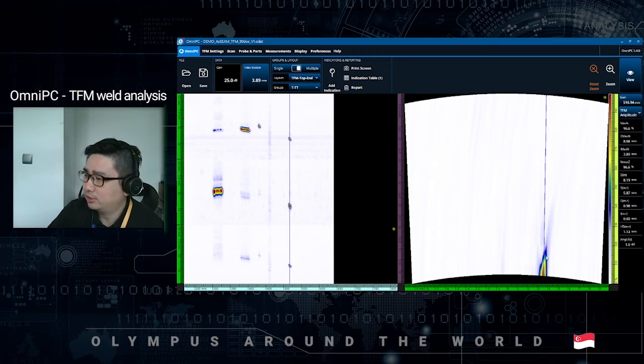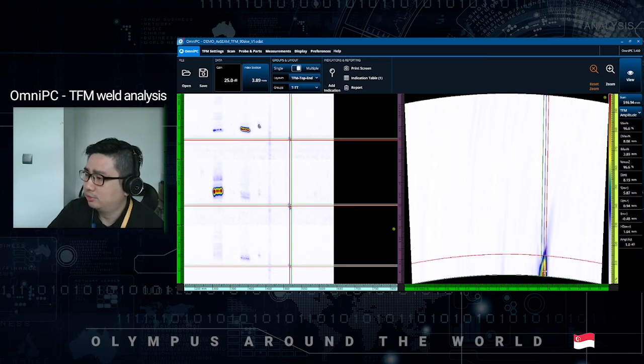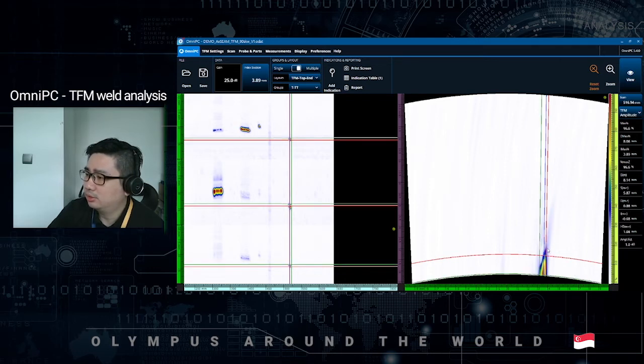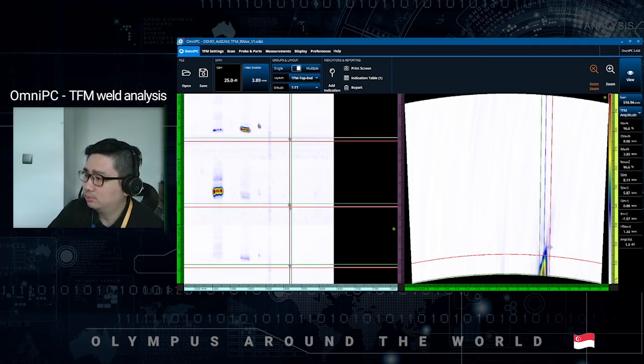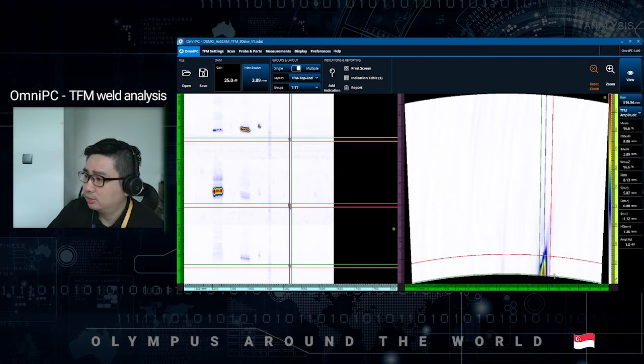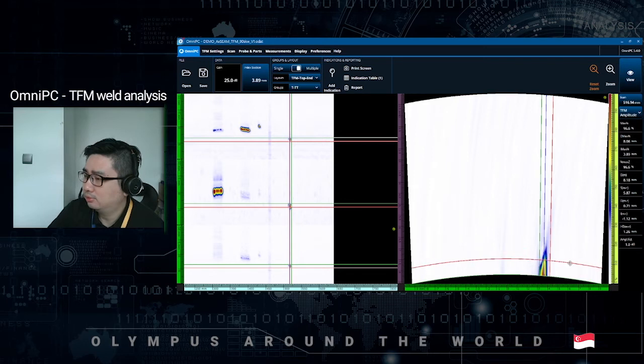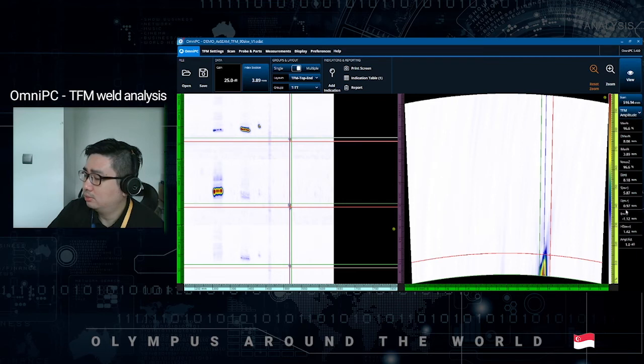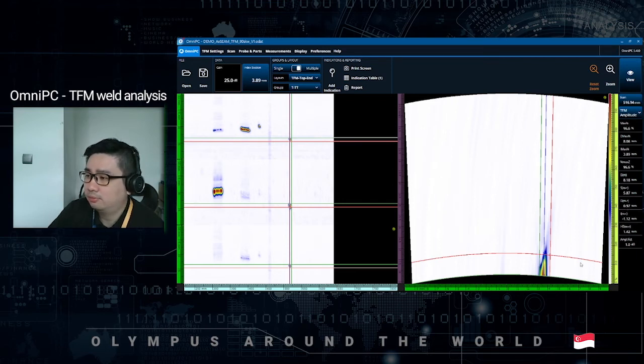First of all, just right click, set your reference, right click again, set your measurement table, and box up the indication as you would on a classic phased array data file. Do the height sizing like this from the back wall. You can see that this is about 0.97, about 1mm height.